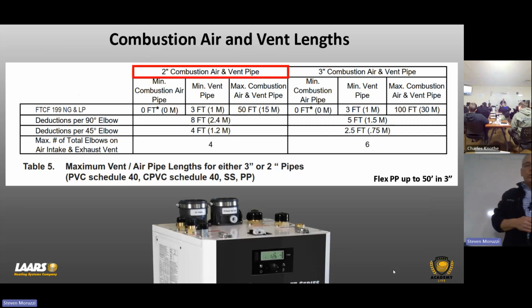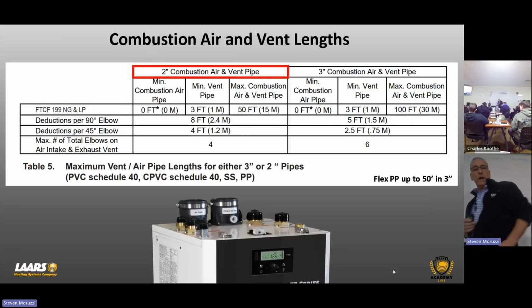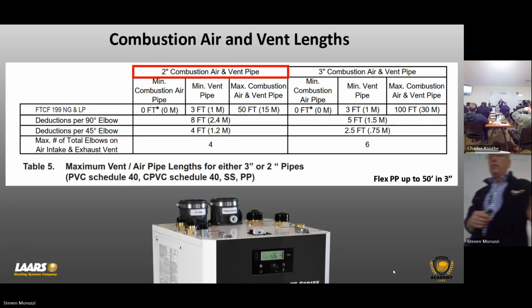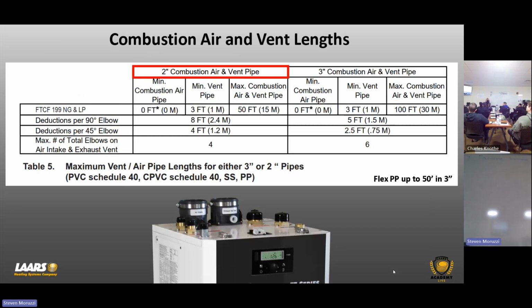So let's talk about 2-inch. 2-inch venting is good for up to 50 feet. Okay. We are going to, on the 2-inch, deduct 8 foot for every elbow, 4 foot for every 45. Okay. 3-inch is good for 100 feet. Okay. In 3-inch vent, and then deduct 5 foot for every elbow, 2.5 for every 45.